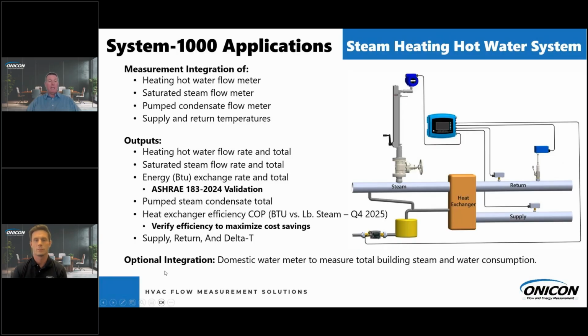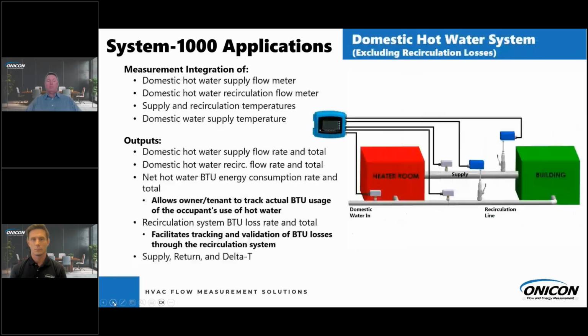And again, you'll get all your temperature information out of your building monitoring system. As an optional integration here, you can bring a domestic water meter in, and you can have a total water consumption for your entire BMS through the System 1000 on one channel. Lastly, we're going to get into the one application here that actually requires both channels of the System 1000 for this installation. This is what we refer to as a domestic hot water system, excluding the recirculation losses.